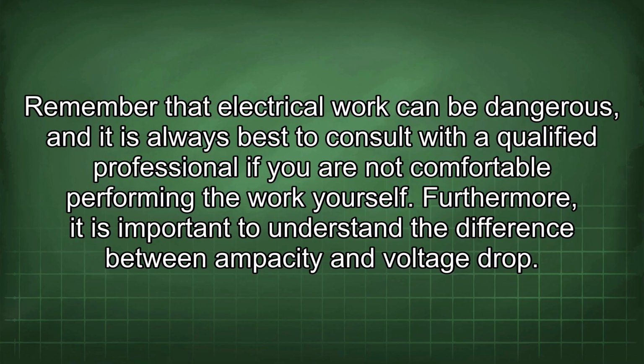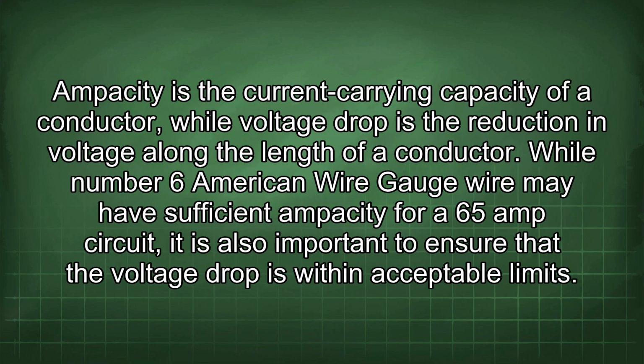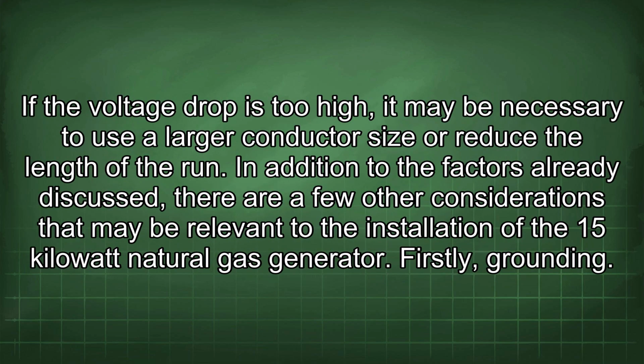Furthermore, it is important to understand the difference between ampacity and voltage drop. Ampacity is the current carrying capacity of a conductor, while voltage drop is the reduction in voltage along the length of a conductor. While number 6 American wire gauge wire may have sufficient ampacity for a 65 amp circuit, it is also important to ensure that the voltage drop is within acceptable limits.